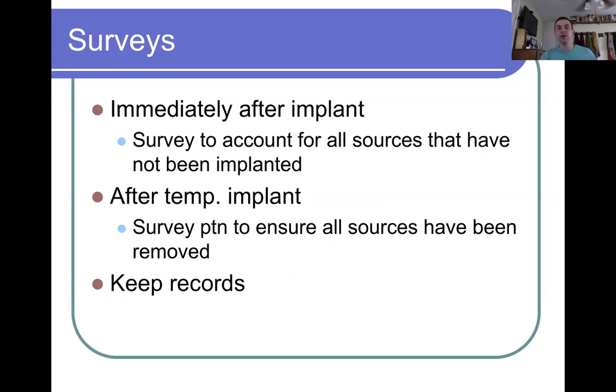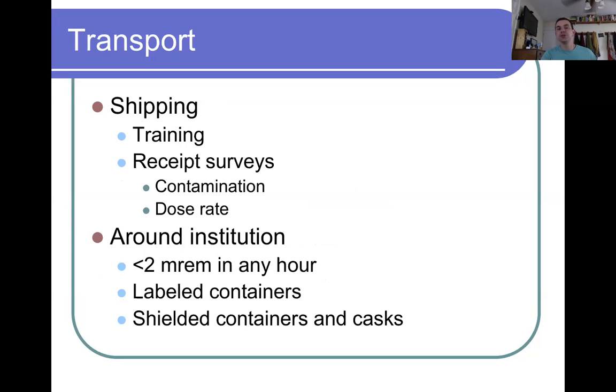So that's what we get to here, is that immediately after the implant is removed, you have to take it out. After a temporary implant, you have to make sure that it came out, whether it's a low dose source or a high dose rate source. That's just a simple way to make sure that there's no potential hazard for anyone in the room, and especially the patient.